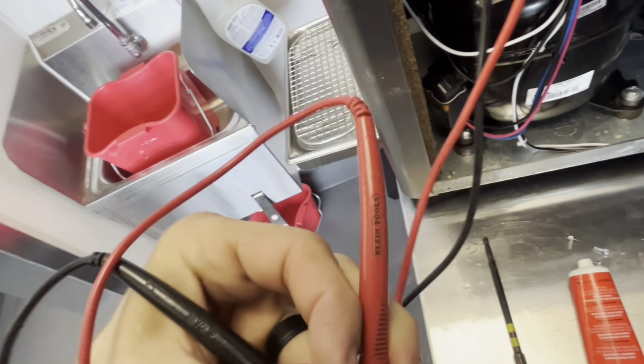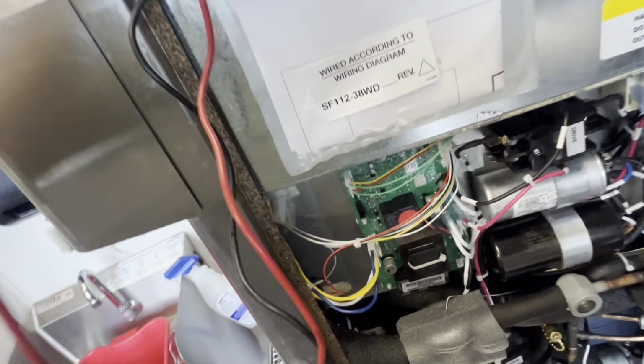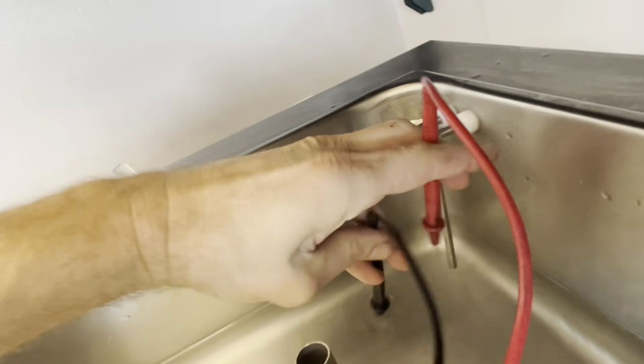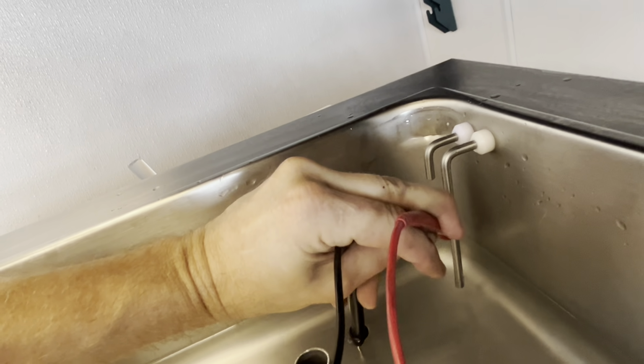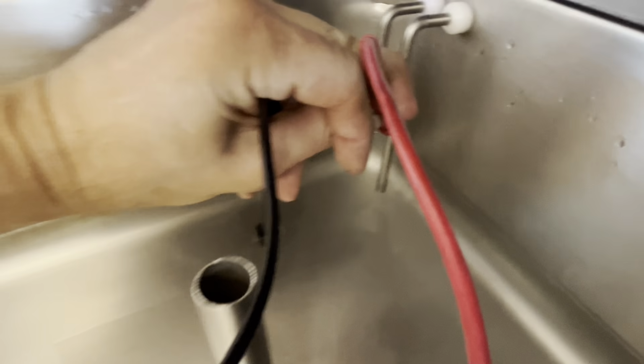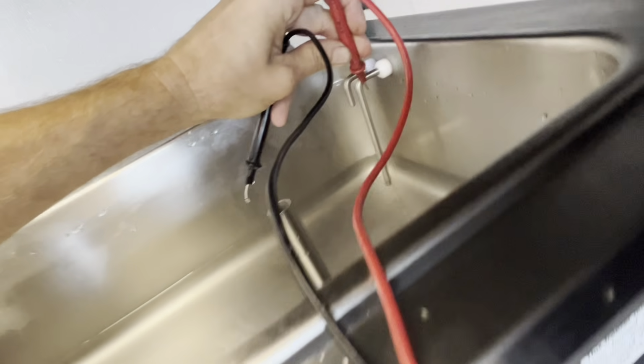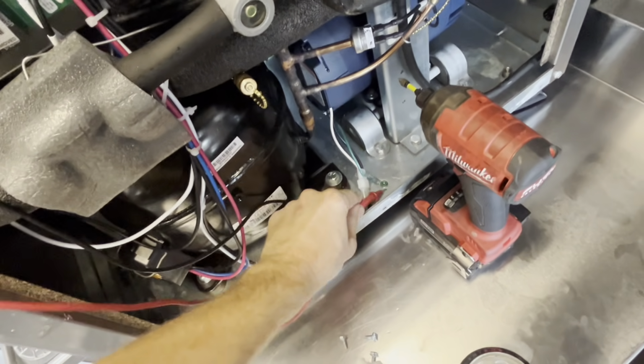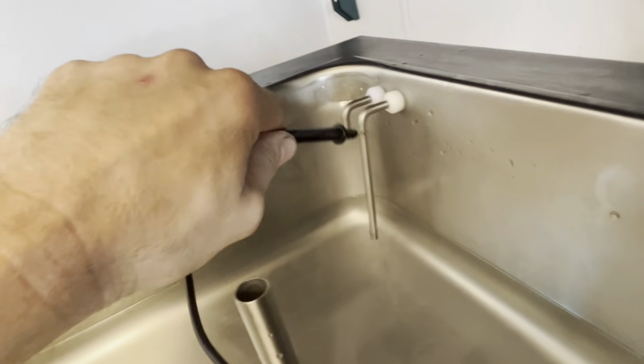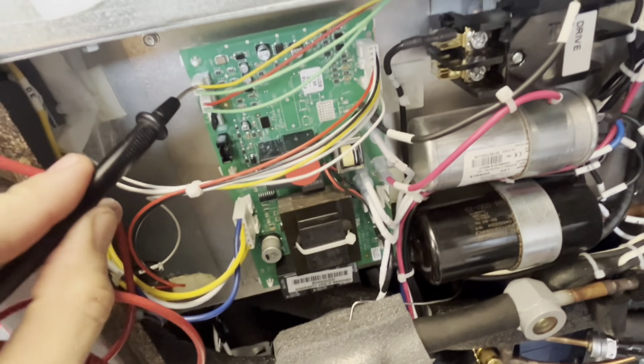It's terrible. So what we were supposed to be able to do was test that we would get tone when we touch the probe to the pan. And I don't have it. We are underwater, but we should get tone from that to any ground. Even when I put it on the frame ground and anything, I get absolutely nothing anywhere. But when we go from the probe to this yellow wire, which I can't do with one hand, I do get tone. So my wire's good.